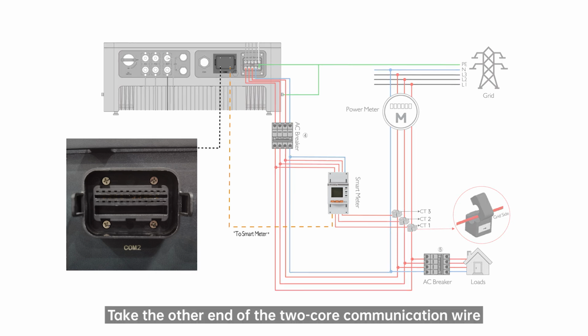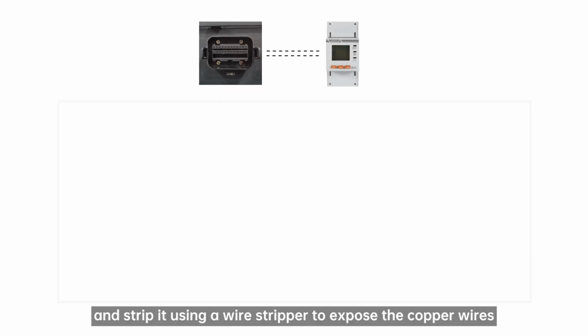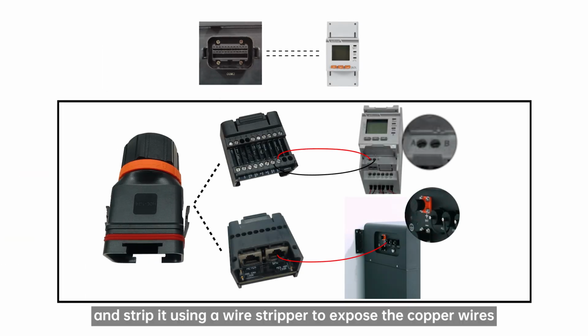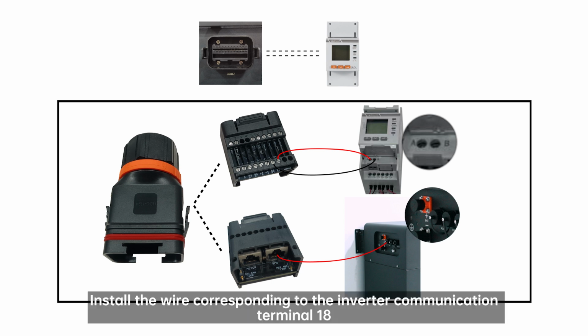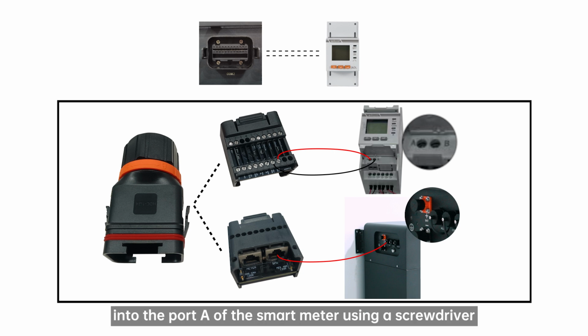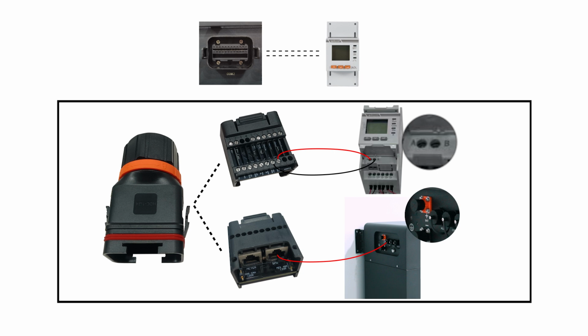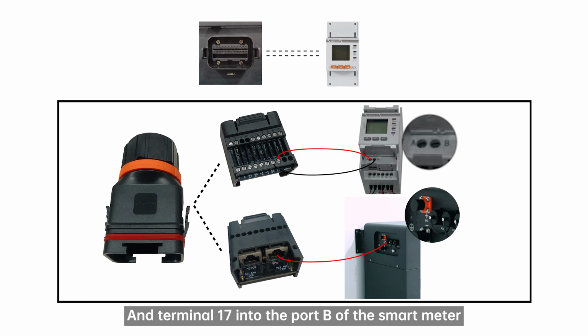Take the other end of the 2-core communication wire and strip it using a wire stripper to expose the copper wires. Install the wire corresponding to the inverter communication terminal 18 into the port A of the smart meter using a screwdriver, and terminal 17 into the port B of the smart meter.